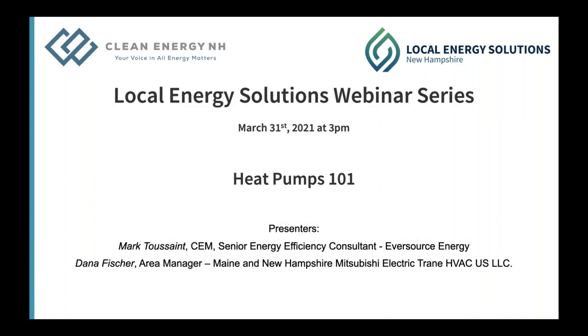Thank you. Let's see. Do heat pump efficiencies degrade over time? As long as the systems are kept clean, the primary reason that they would degrade would be just because the coil is getting clogged and it needs to be cleaned out. That's a primary loss of efficiency. If the system is installed properly, there shouldn't be any degrade in the capacity of the system over time.